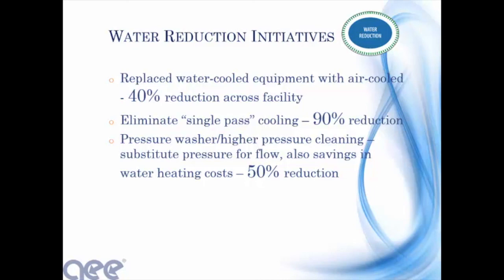We have another area doing single-pass cooling now at a facility in New Orleans, where we have an air compressor — anytime the temperature gets over 80 degrees, we're dumping city water down the drain. But the chiller plant we just installed is being tied into the cooling of that air compressor, so we're going to eliminate that single-pass cooling by using the chiller plant instead.